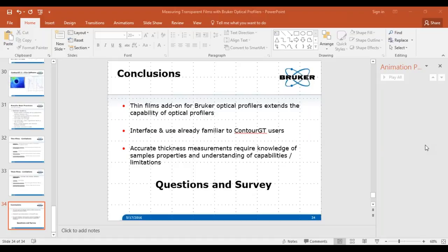A question about multi-layered thin films: when there are more than two or three thin layers, that's going to be very difficult. Especially when you get to something that's basically going to look like a graded index, we don't have the ability to pick apart those multiple interfering reflections. We're limited to two reflections at a time — so one thick film, or two thin-film interfaces. Unfortunately, we can't measure multi-layer thin films with this package.